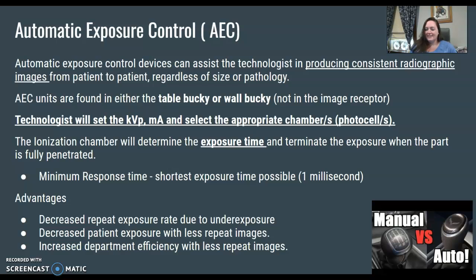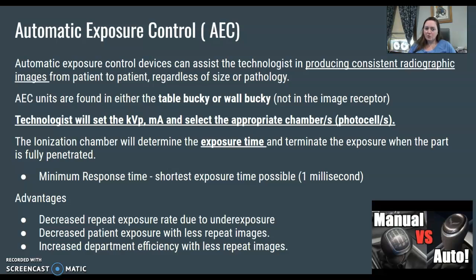Where is the AEC? It is in your wall bucky and table bucky. The AEC is not in the image receptor itself. When you go to do portable x-rays, you can't use your photo timing option. You have to set your own mAs and kVp. You have to be in your rooms with a table bucky or a wall bucky to have access to your AEC.